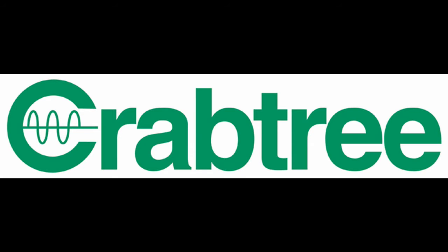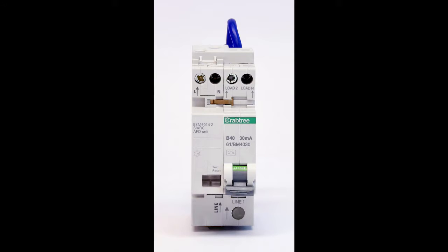New regulations in the 18th edition. With the release of the 18th edition of the wiring regulations, which was published on the 1st of July 2018, a new type of circuit protection device was included under Regulation 421.1.7 regarding AFDDs, which stands for Arc Fault Detection Device. Starbreaker consumer units are the only consumer units that can accept AFDDs without the need for special busbars or assemblies, or on-site adjustments. Furthermore, because the busbar hasn't changed since its launch, AFDDs can be instantly fitted to any Starbreaker consumer unit, regardless of its age.